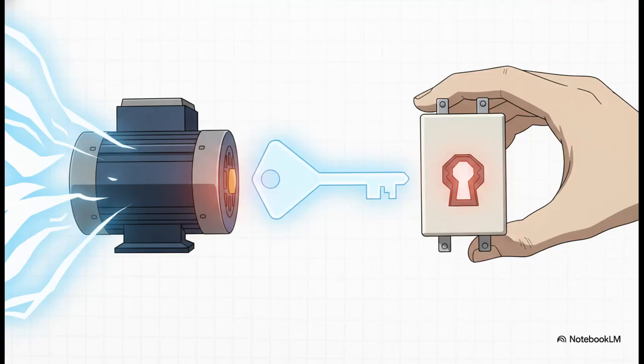And this right here is probably the most important thing to take away from all this. You cannot, I repeat, cannot just swap in any old potential relay that looks like it fits. If a motor is designed to only generate 270 volts of back EMF, but you install a relay that needs 330 volts to pick up, that relay will never, ever open. You have to use the exact relay specified by the manufacturer for that exact compressor. The ratings have to match.